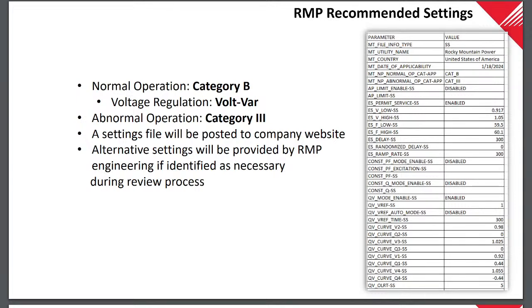With these settings, it won't be a situation where the contractor doesn't know what settings to use. They'll be there, and the way I see it, it'll come from the engineering review. There will be a process where, as we go through the review, whoever's doing it selects which settings file needs to be uploaded to that inverter. I'd imagine the majority will be what we call the recommended settings, which is on that slide. There's a small tweak we're going to recommend for the voltage, the volt-var settings, and we'll go over that in the next slide. If there are alternative settings, we'll provide those as well.